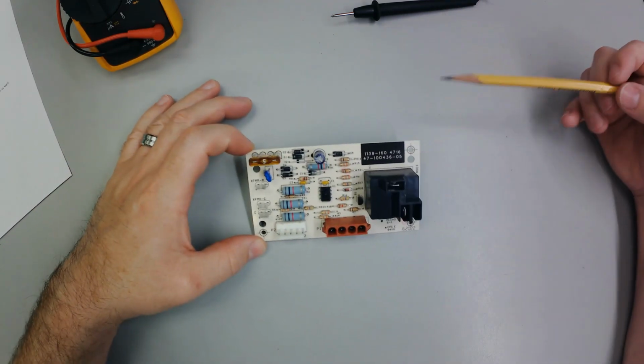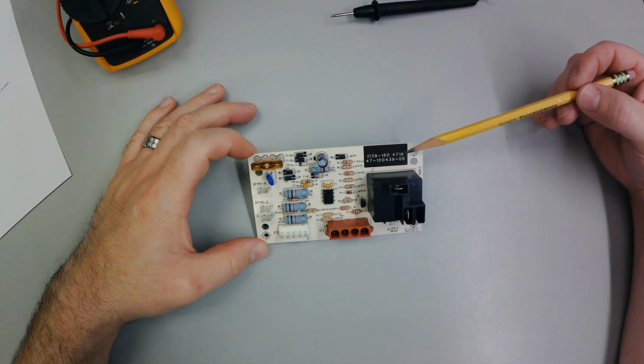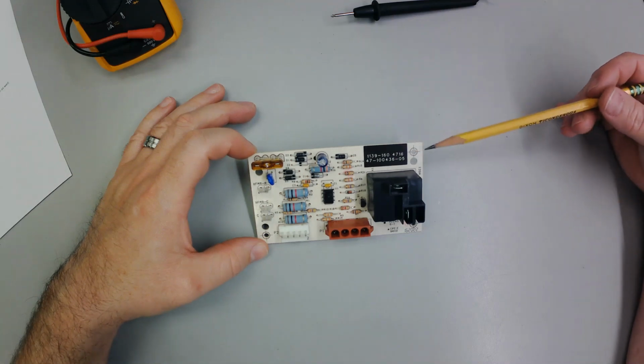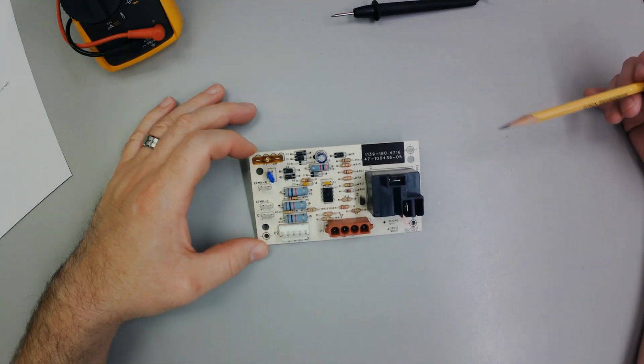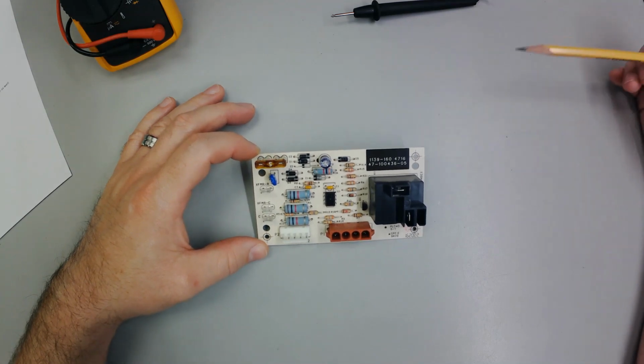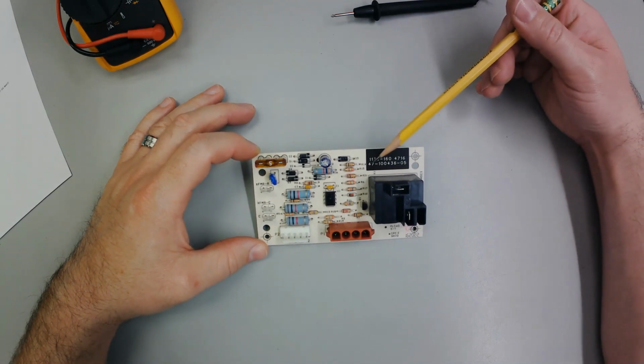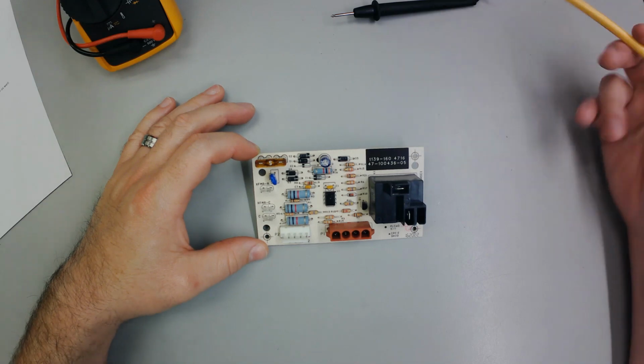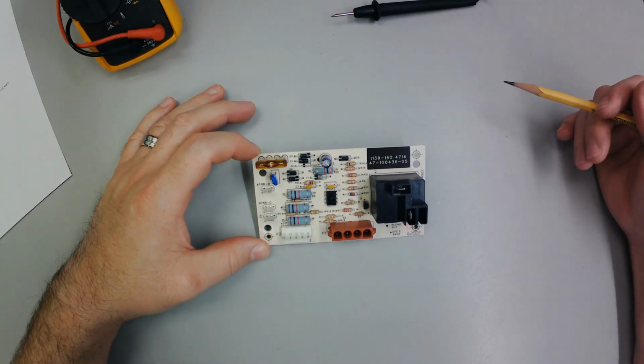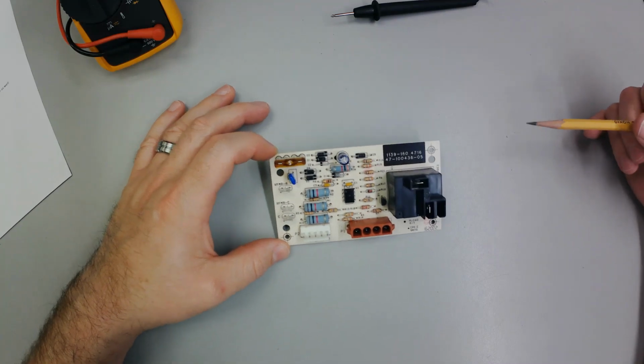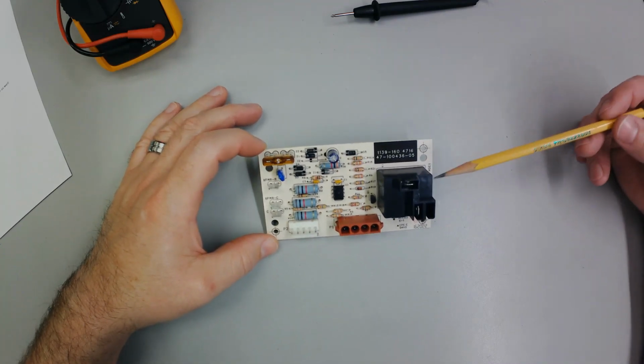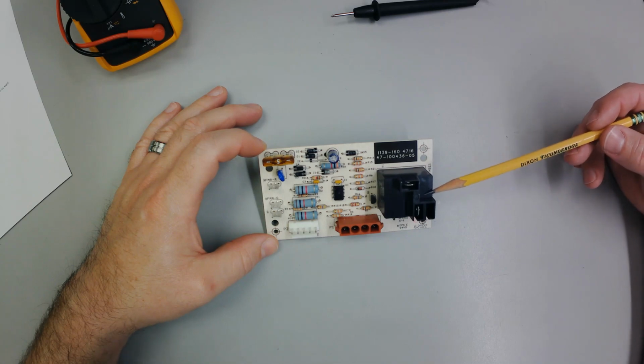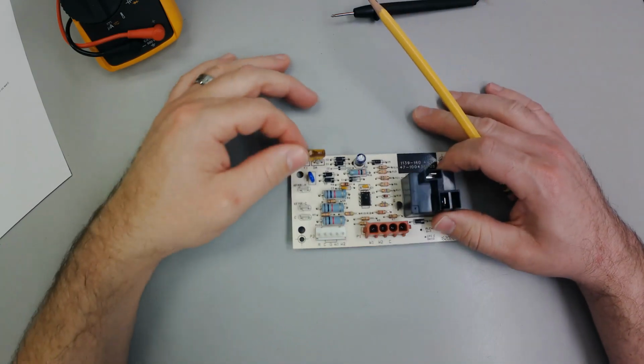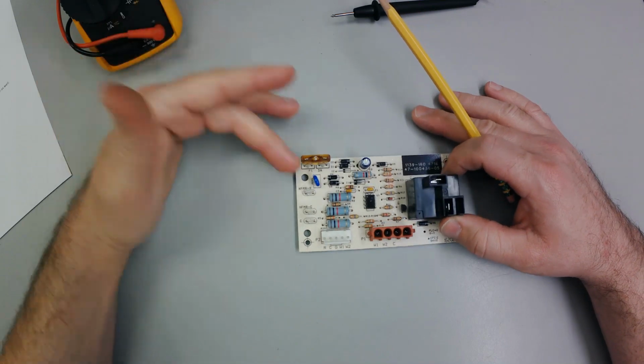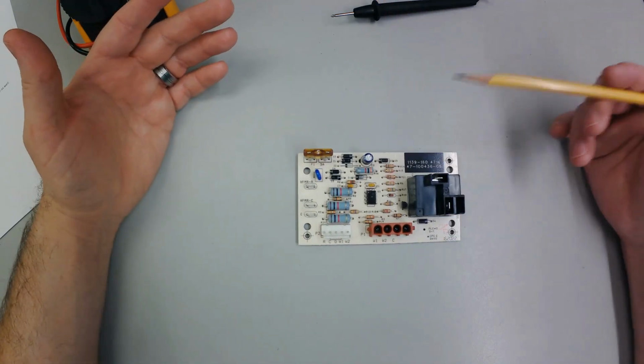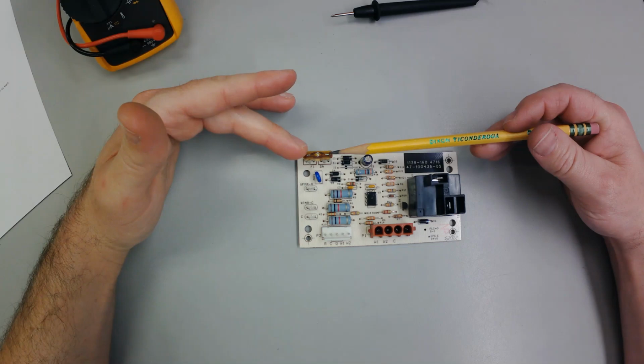So this is a Rheem. You can see the part number up here. It's a 47-100436-05, and I'm sure there's some superseded version where it's been replaced by an 06 model or whatever it is. But that's the part number right here in this little black square on the board. If we look at it and liken it to the Goodman, we're going to see some similarities. We're going to see this black relay here. That's the physical fan relay. We're going to see this fuse. That's the 5-amp fuse. Anytime you see a fuse, it's there to protect the 24-volt transformer circuit.